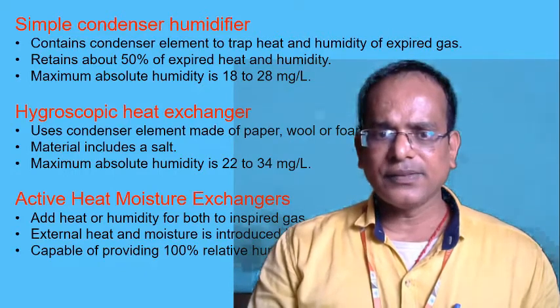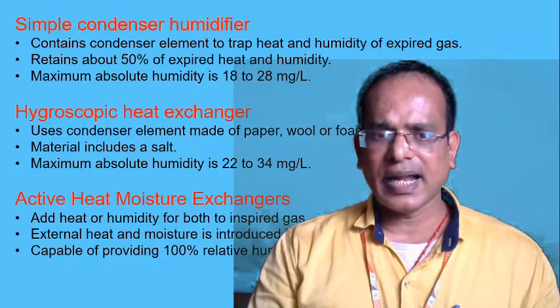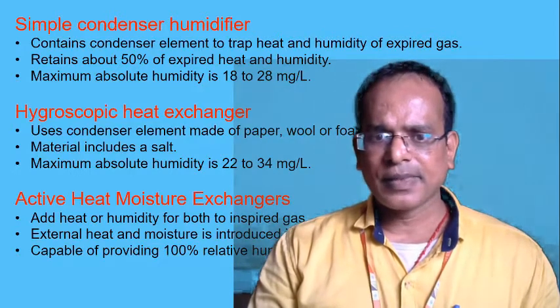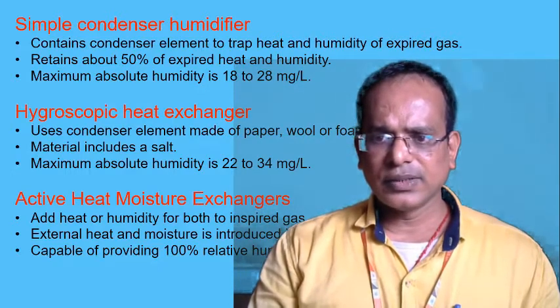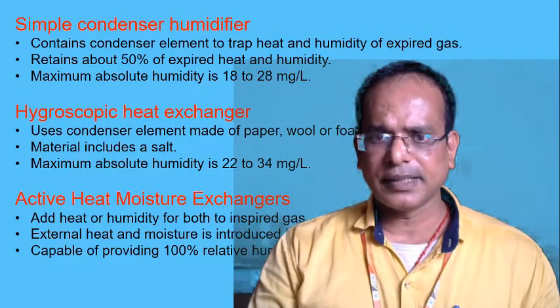Active heat and moisture exchange adds heat or humidity, or both, to the inspired gas. External heat and moisture is introduced into the inspired gas, capable of providing 100% relative humidity at BTPS.